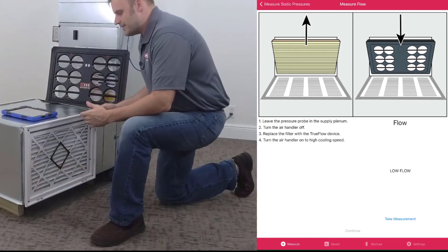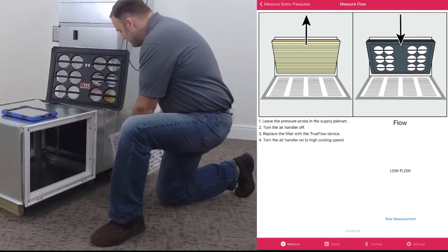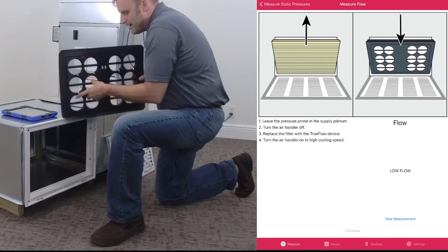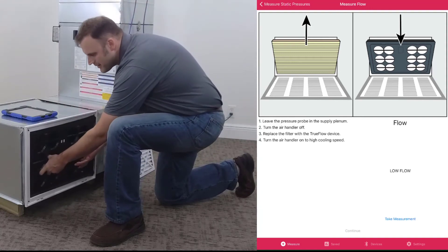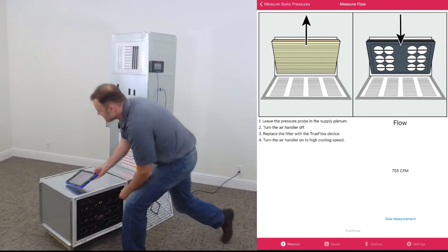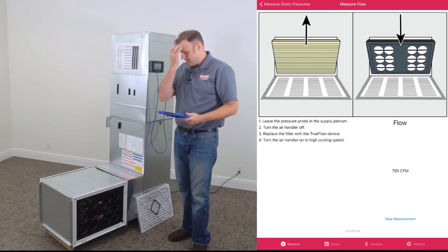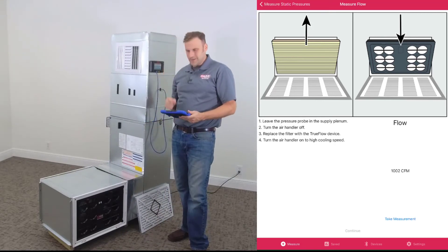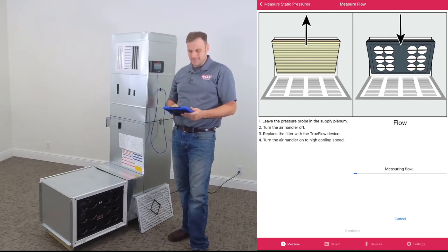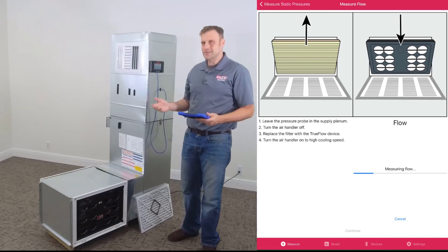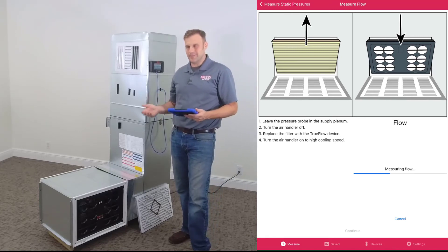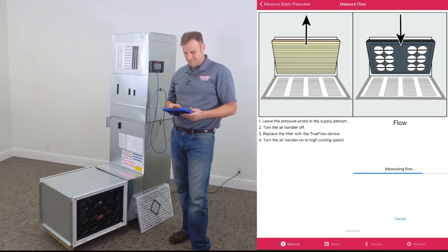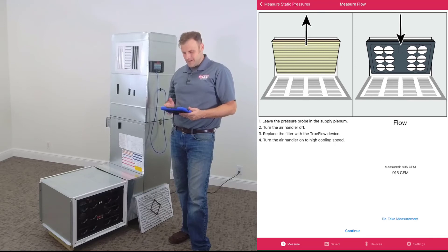Okay, at this point we take the filter out, we install the digital TrueFlow grid. Okay, with the grid in place, we can click Take Measurement. There we go, again we're taking those multiple readings to give you an average and a good accurate measurement. And there we go.